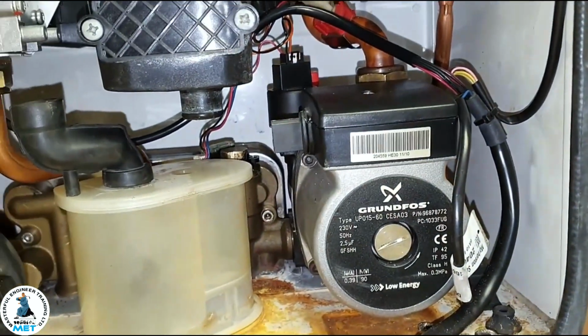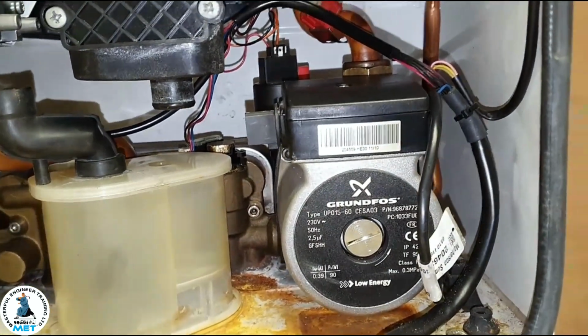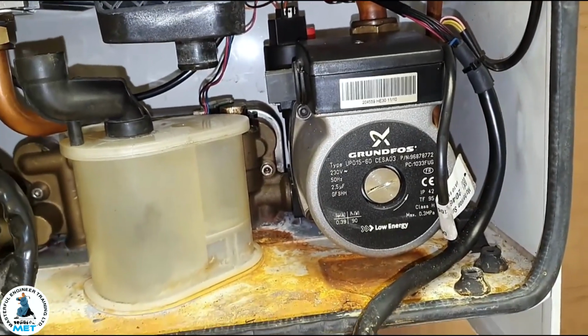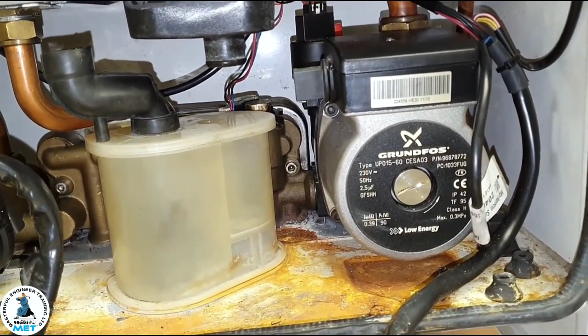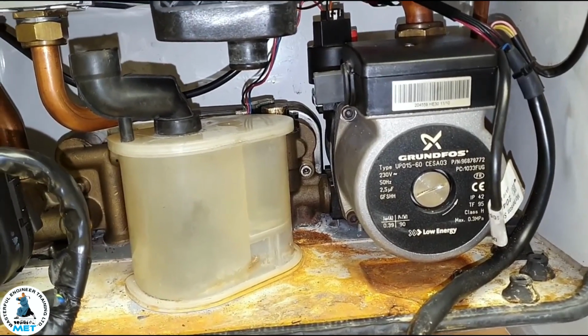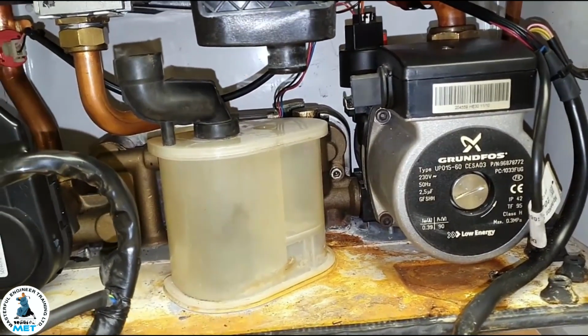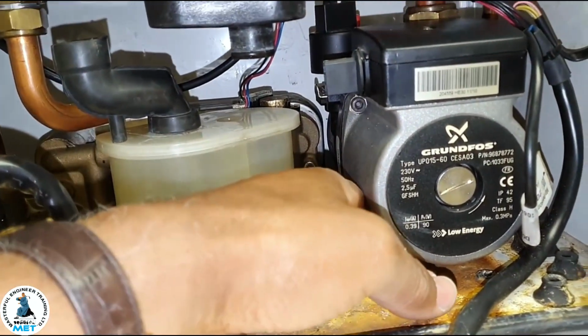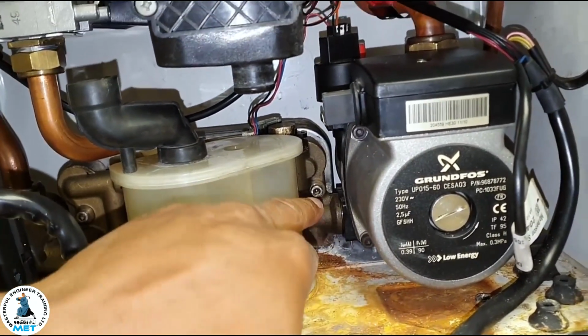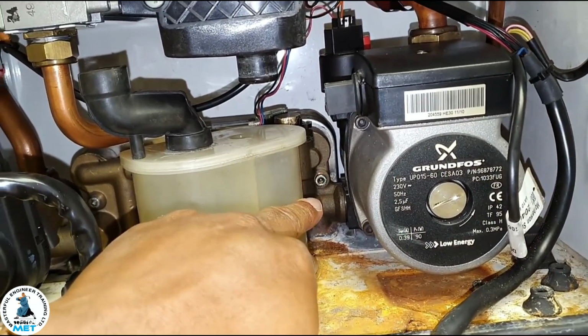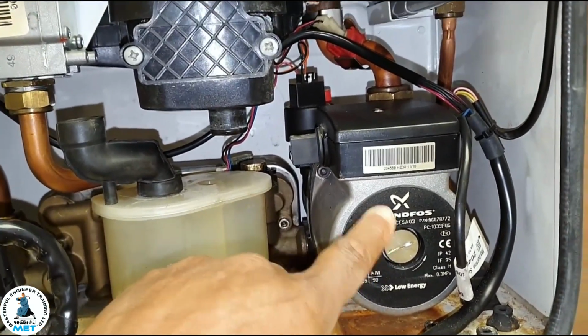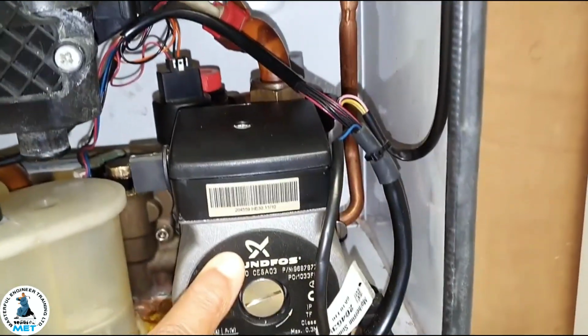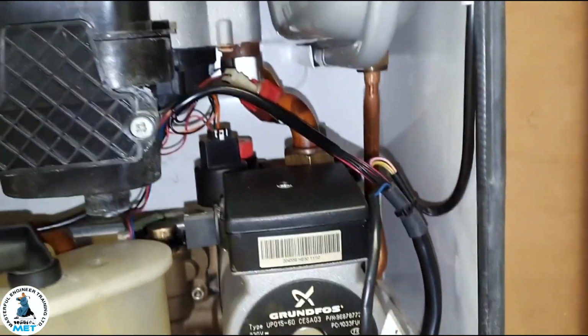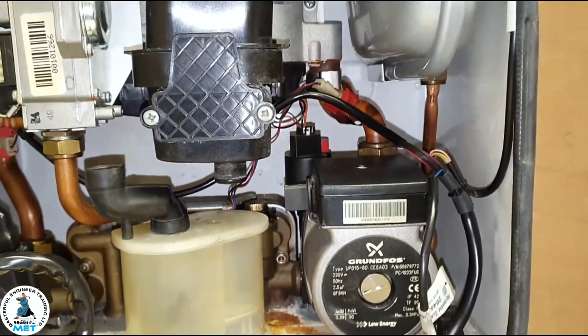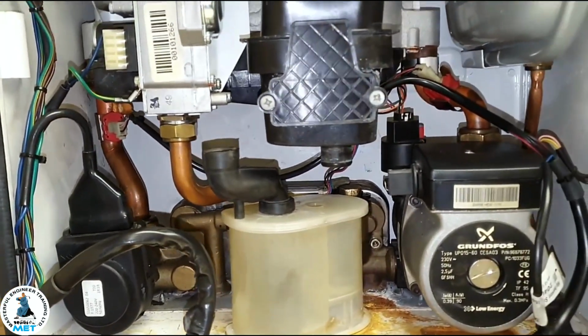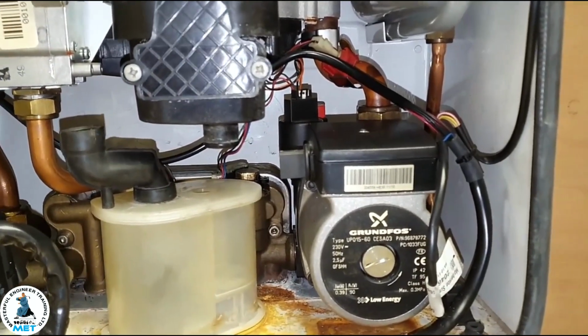So you'd have to take the pump body out, which means undoing the connections underneath the boiler, a total drain down, primary drain down, and the cold water inlet. Part of the pump connects into the manifold, which is the cold water inlet, so you've got to turn it off. It's quite an extensive job just because that pipe's blocked. It looks nice and easy, but it's not. It's quite a comprehensive boiler repair exercise.